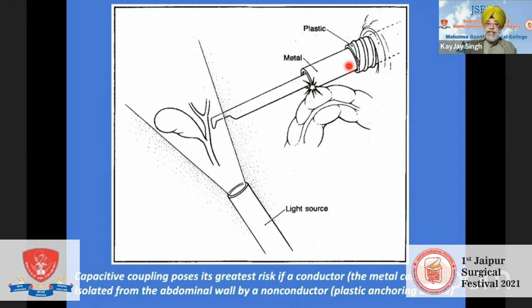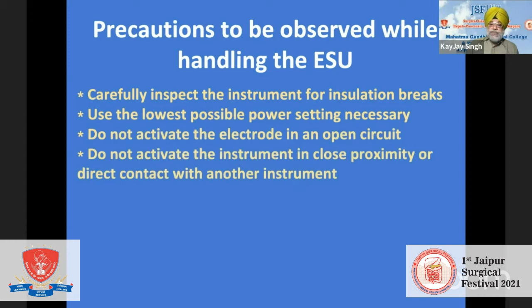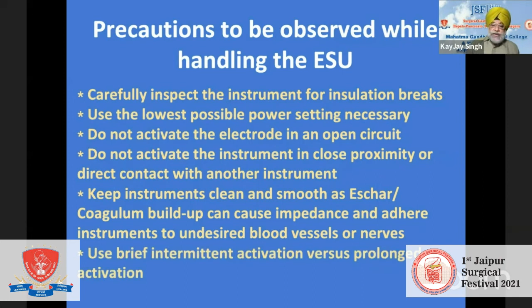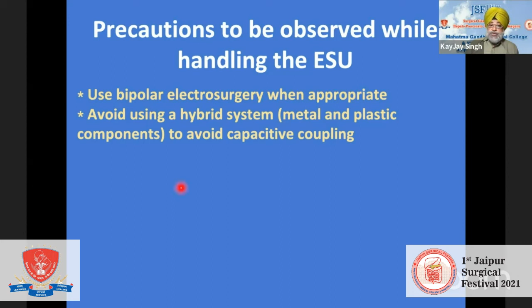So, precautions: carefully inspect the instrument for insulation break. Use the lowest possible power setting necessary. Do not activate the electrode in open circuit. Do not activate the instrument in close proximity or direct contact with another instrument. Keep instruments clean and smooth, as eschar coagulum buildup can cause impedance and adhere instruments to undesired blood vessels or nerves. Use brief intermittent activation versus prolonged activation. Use bipolar whenever appropriate. Avoid using a hybrid system, metal and plastic components, to avoid capacitive coupling.